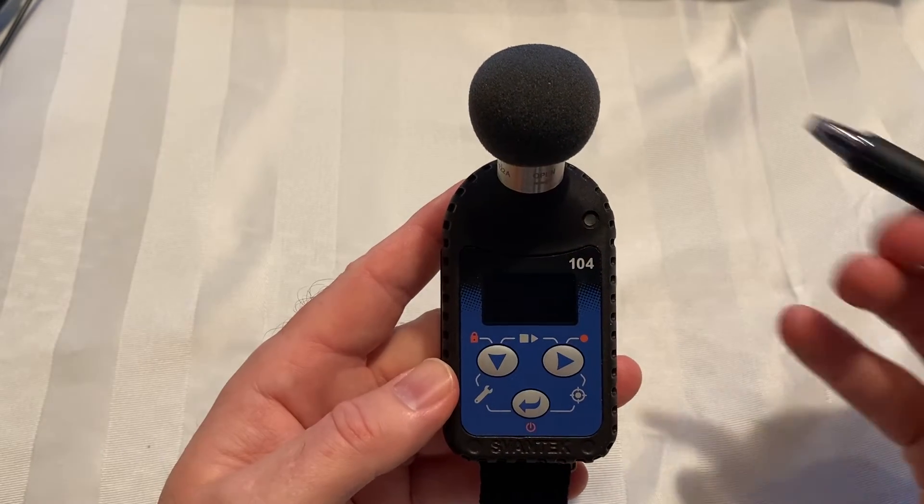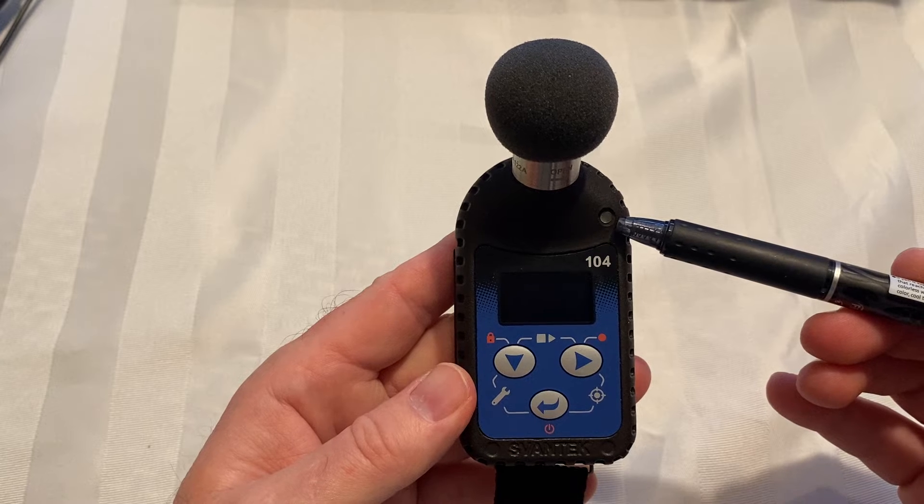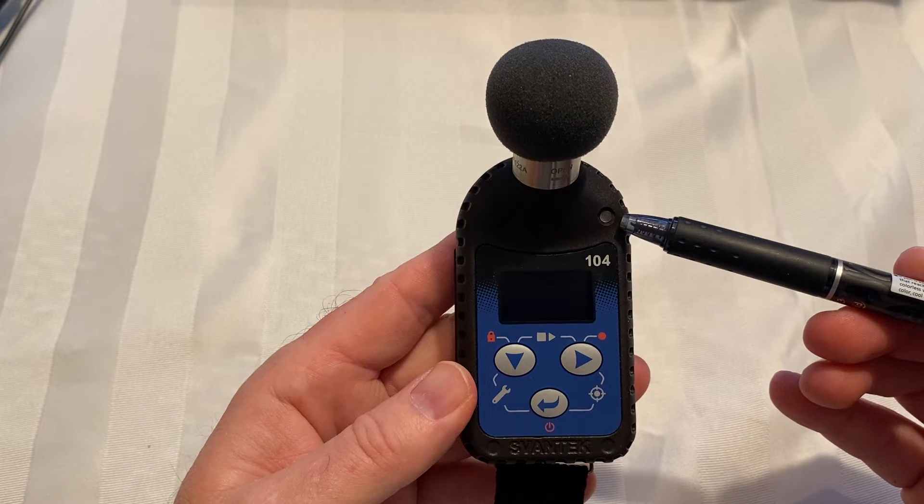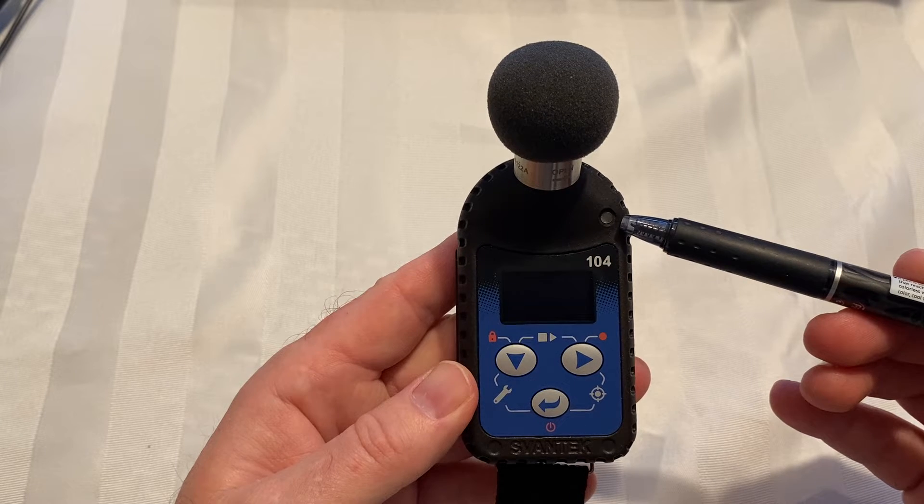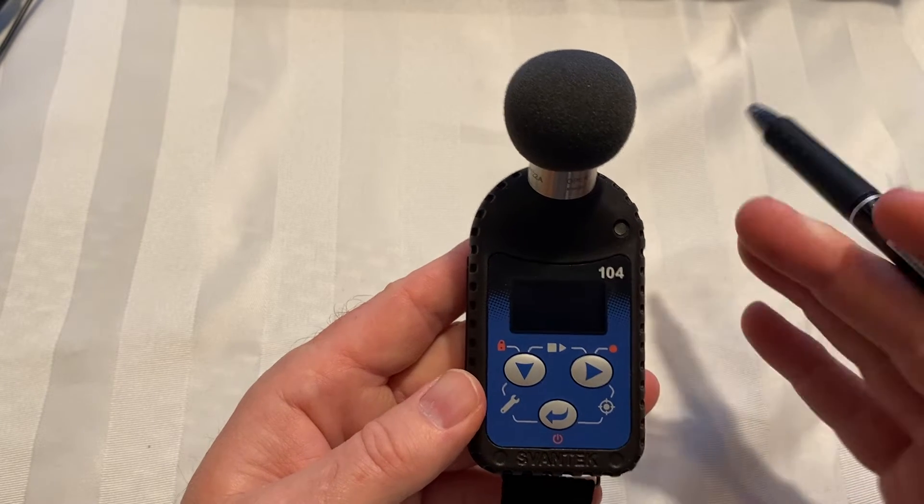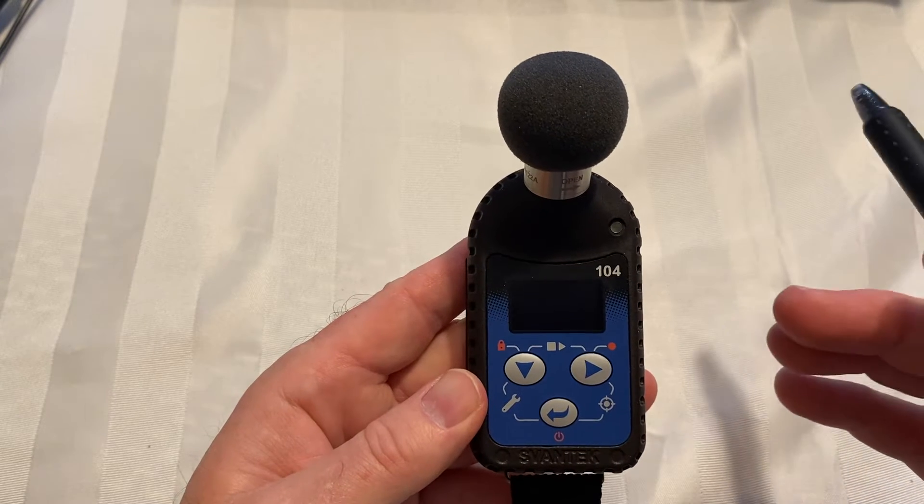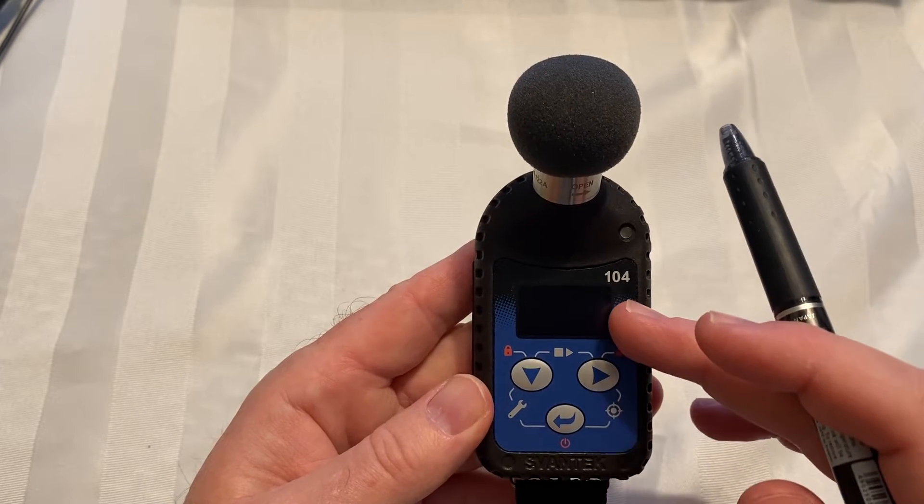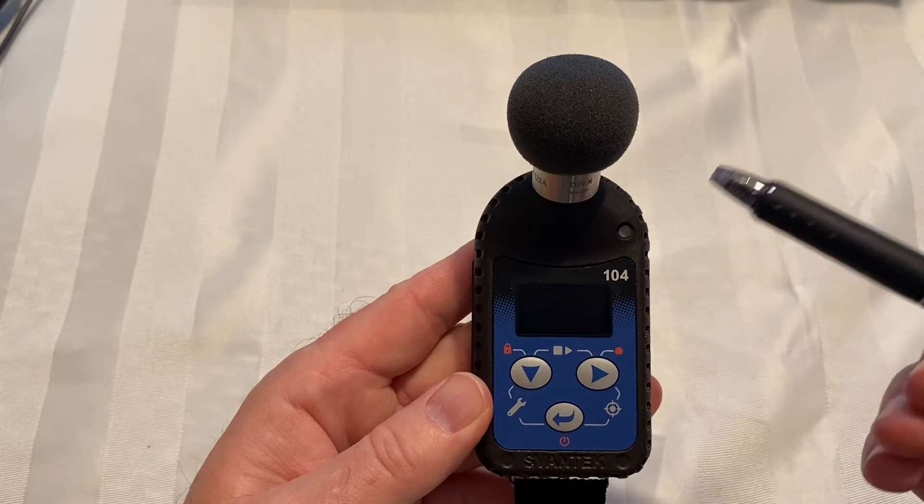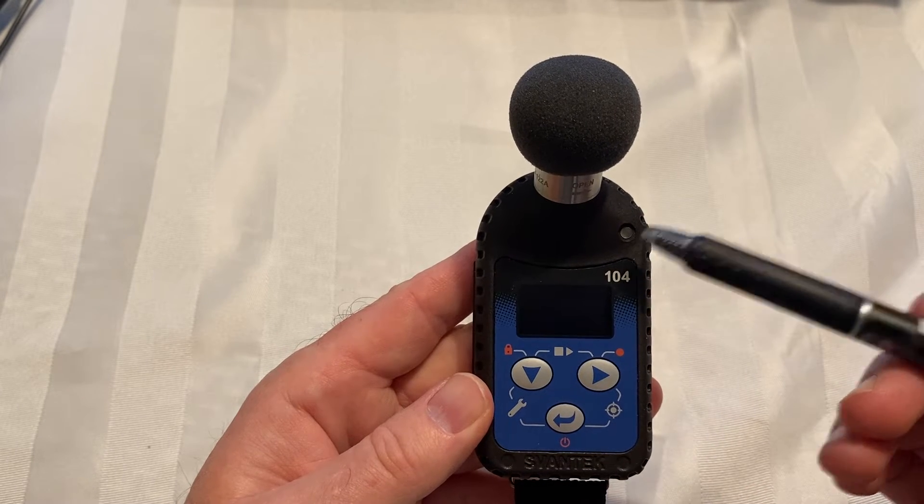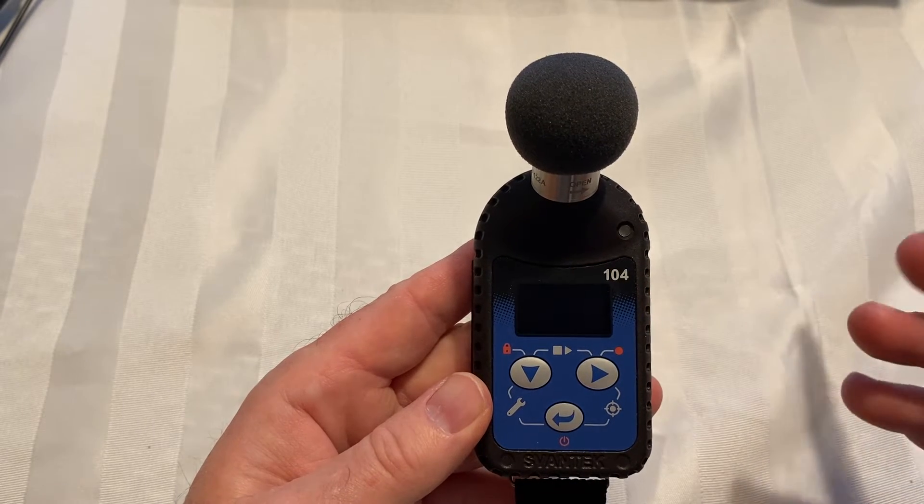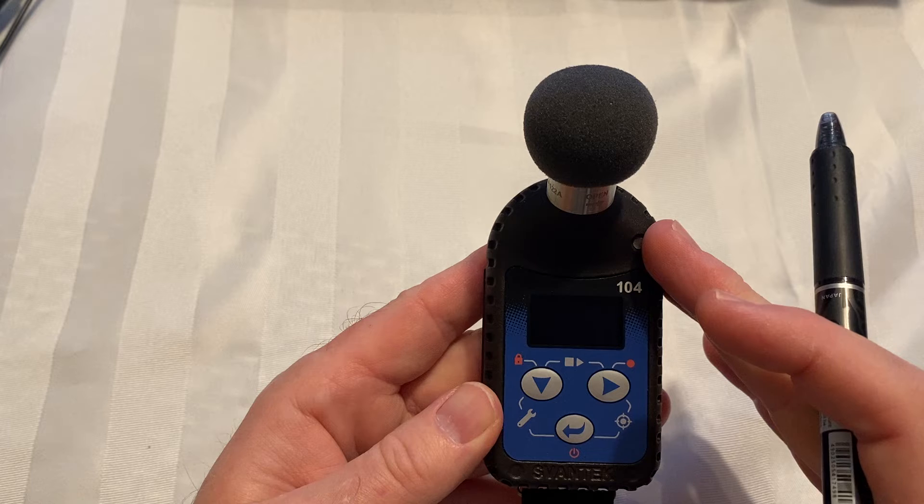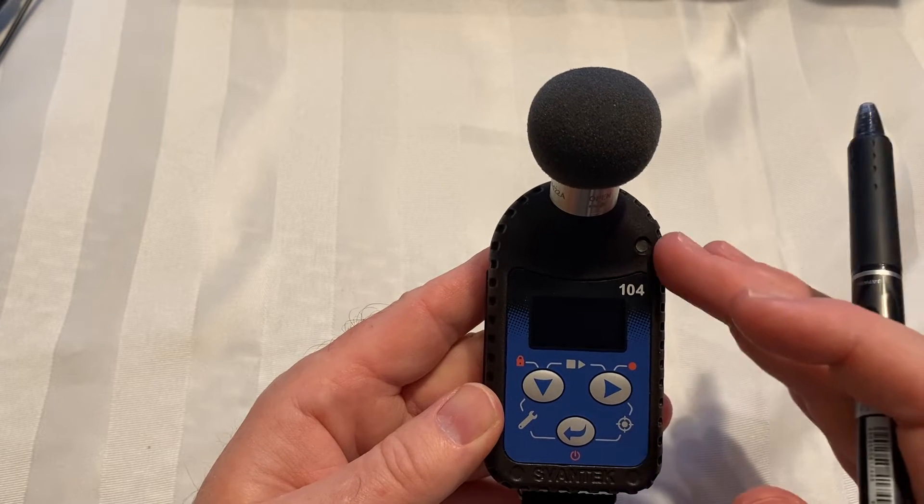Now I'll also show there's a little light here. That light, if the dosimeter is stopped, will be yellow or amber. If it's measuring, it'll blink green. And if there's an alarm, like if the unit's knocked, or for example you could set it so that if the person wearing it hits 100% of their dose, when you walk up you'd see that it's red - that would let you know they've exceeded their dose of noise. So this light can be amber, green, or red.